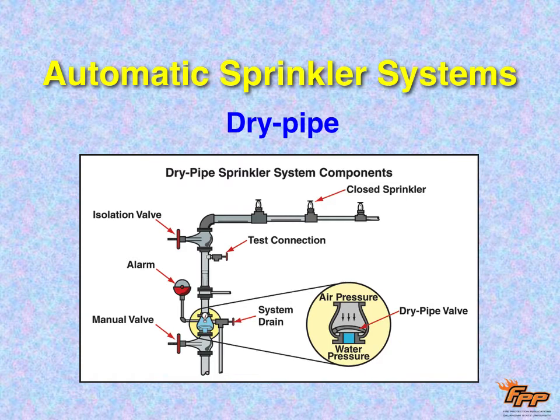In a dry pipe system, there isn't water in all of the pipe, but the sprinkler heads are the exact same. What's important to understand with both a wet pipe and a dry pipe system is that only the sprinkler heads that are exposed to the heat are going to open up and water comes out. So the water only comes out where the fire is, where the heat is. They're both similar in that sense. The sprinkler heads work the same way. The main difference is that there's a valve, and you can see the blow-up of that valve there. On one side, you've got water pressure. On the other side of the valve, there's air pressure, and there's air pressure throughout all of the pipe in the building on the air side. So the air pressure has to be greater than the water pressure to hold that valve down.